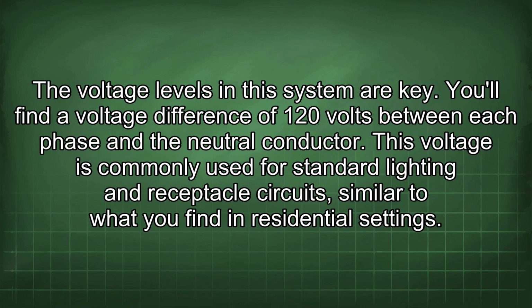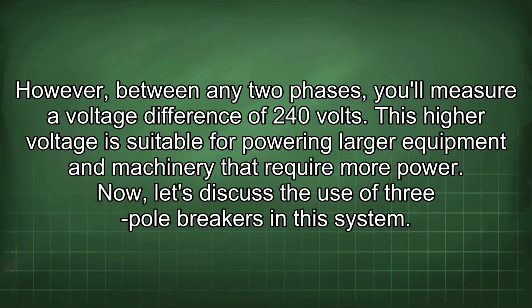The voltage levels in this system are key. You'll find a voltage difference of 120 volts between each phase and the neutral conductor. This voltage is commonly used for standard lighting and receptacle circuits, similar to what you find in residential settings. However, between any 2 phases, you'll measure a voltage difference of 240 volts. This higher voltage is suitable for powering larger equipment and machinery that require more power.